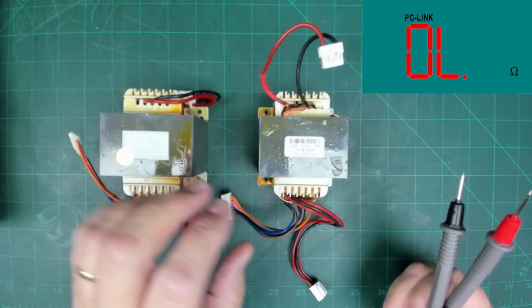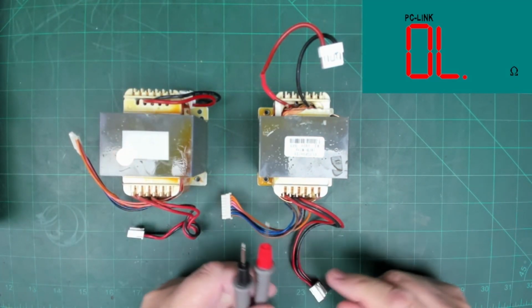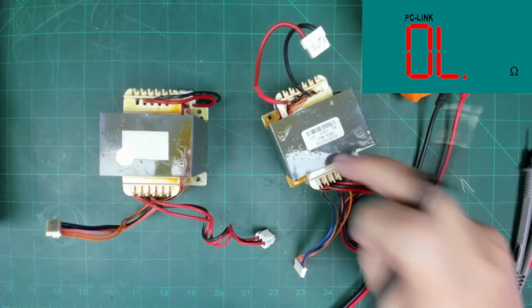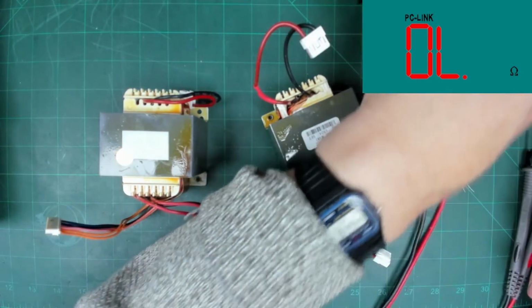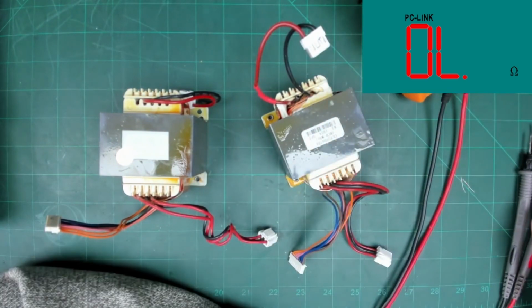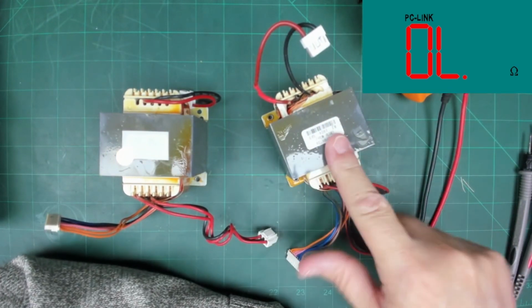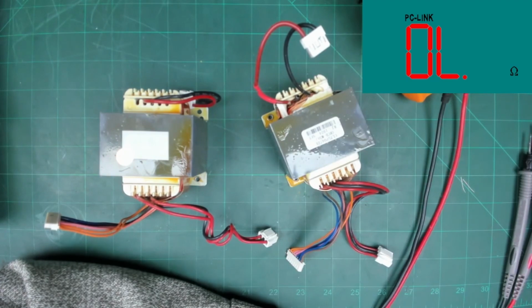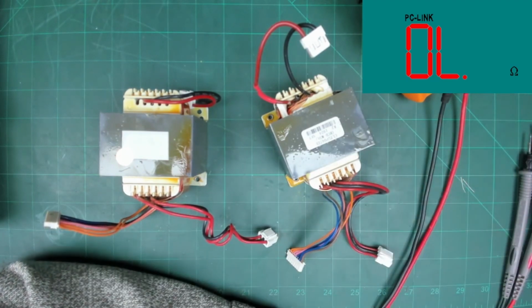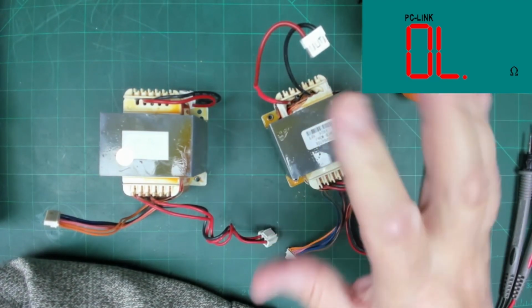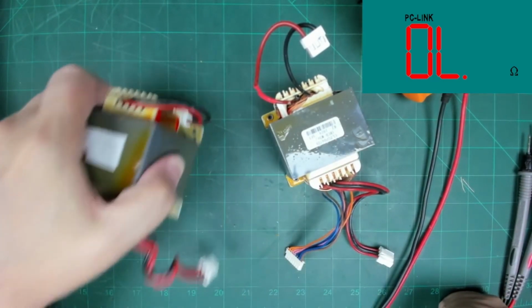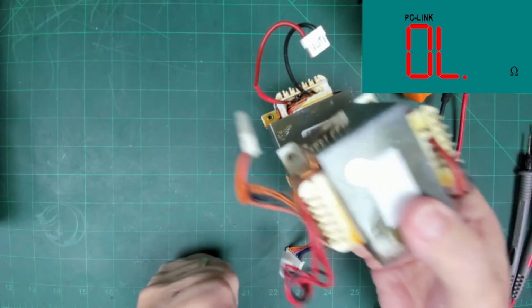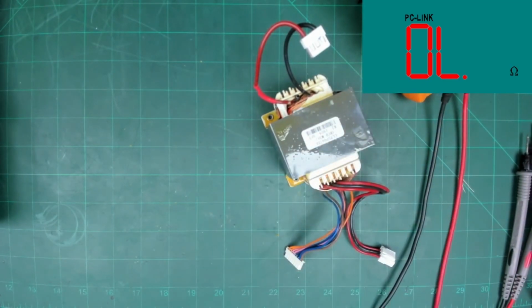I'm not going to check the resistance of the primary - I'm pretty sure that's probably okay - but I will check the secondaries. I'm going to say that transformer's probably okay. I think if we had a shorted turn in those windings, it would have really shown up as a zero, because that's what shorted turns do, unless it does it when it gets hot. I don't want to put this in yet until I've proved there's a fault elsewhere, so I'm going to put this new transformer to one side.